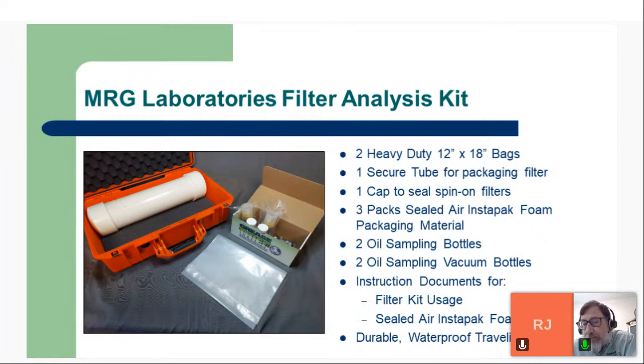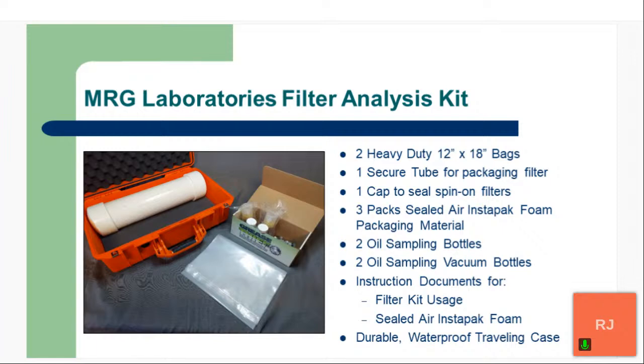Yeah, definitely. I can think of a couple examples. The first one, as you kind of mentioned, was a filter that was damaged in shipping to the laboratory. The filter was not inside of an overpack or a durable container. It was inside of a plastic bag, which was great for the beginning part of the process, but then they put it just inside of a cardboard box that was roughly the same size. During traveling, it got another box dropped on it, and that damaged the area that they had actually sent us a picture of wanting us to investigate.